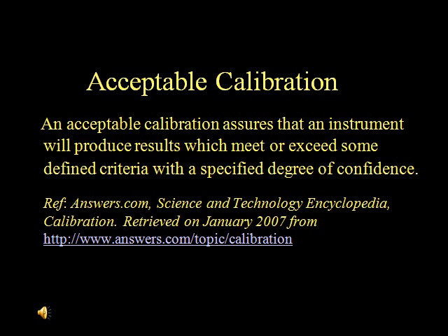Once an initial calibration has been created, we must determine what makes an acceptable calibration. An acceptable calibration assures that an instrument will produce results which meet or exceed some defined criteria with a specified degree of confidence.